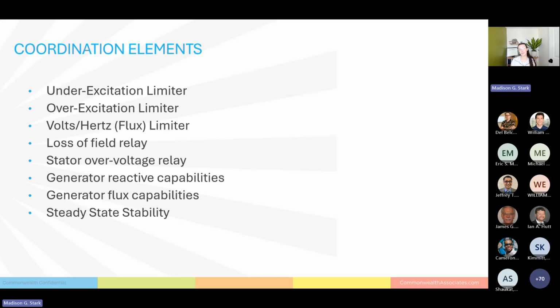As far as what actually gets coordinated on the generator, this is where we're getting into how this operation ties into PRC 19 specifically. You have a few limiters that you're working with. You have your under excitation limiter, your over excitation limiter, and then your volts hertz limiter or your flux. Your volts hertz ratio is really your flux that you're talking about. You have a couple of relays. You have your loss of field relay or relays, depending on the system. And then you have your stator overvoltage relay.